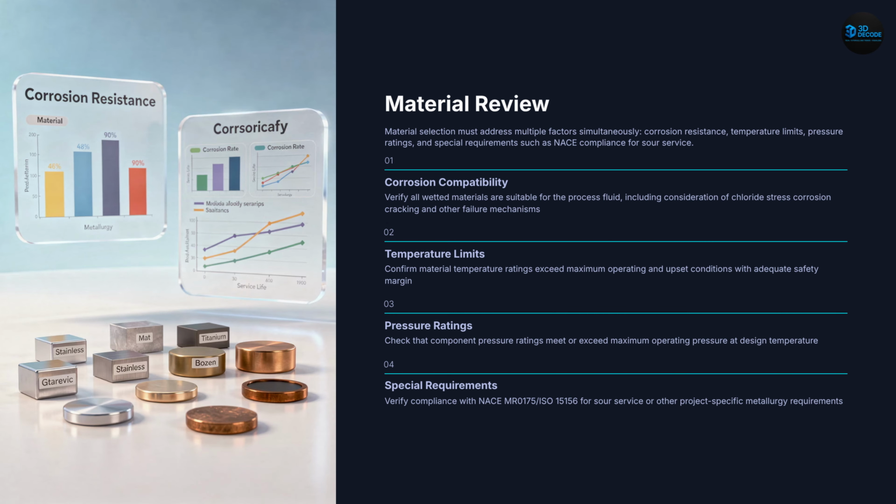Slide 10. Material review. Verify materials are compatible with fluid. Check corrosion resistance, temperature limits, and pressure ratings. Also confirm NACE requirements if applicable.